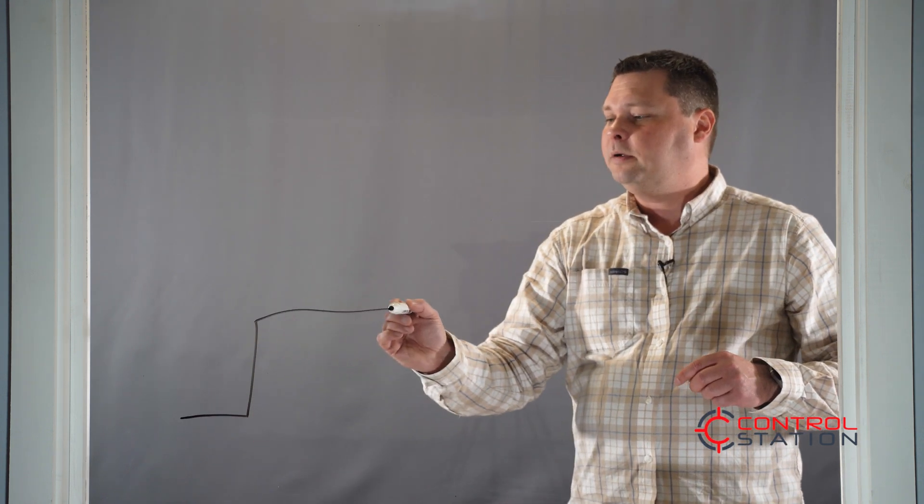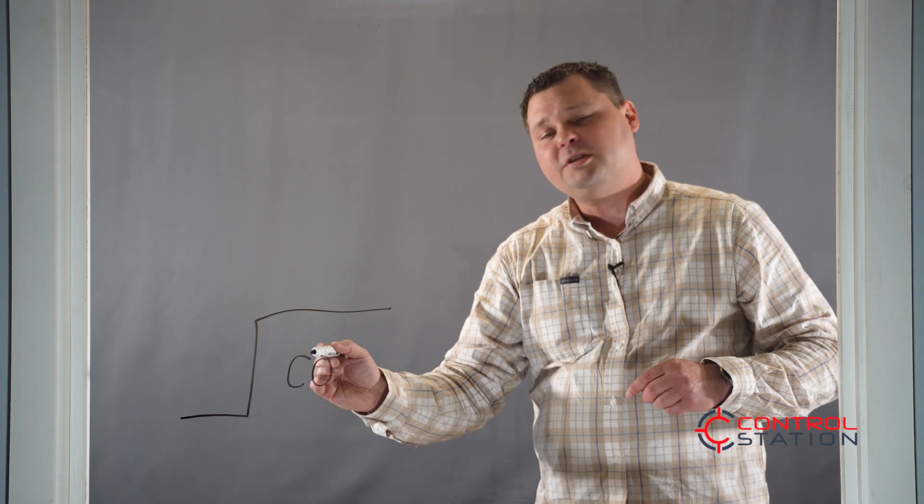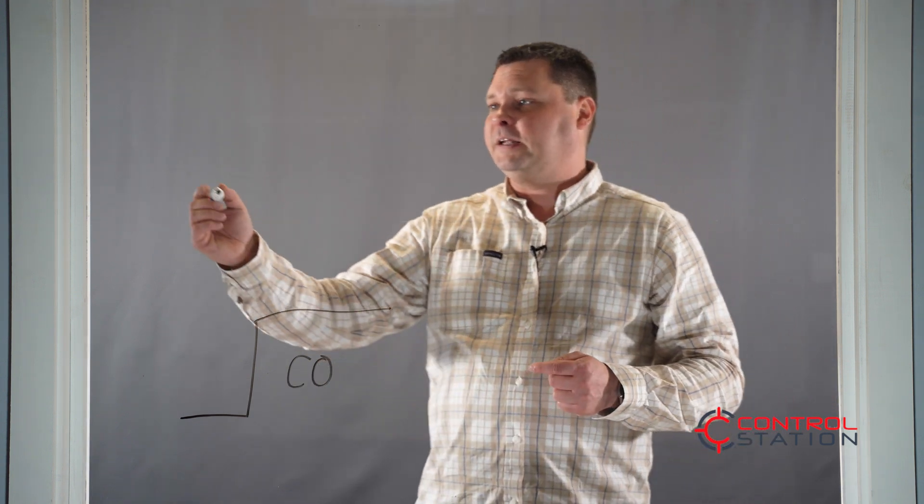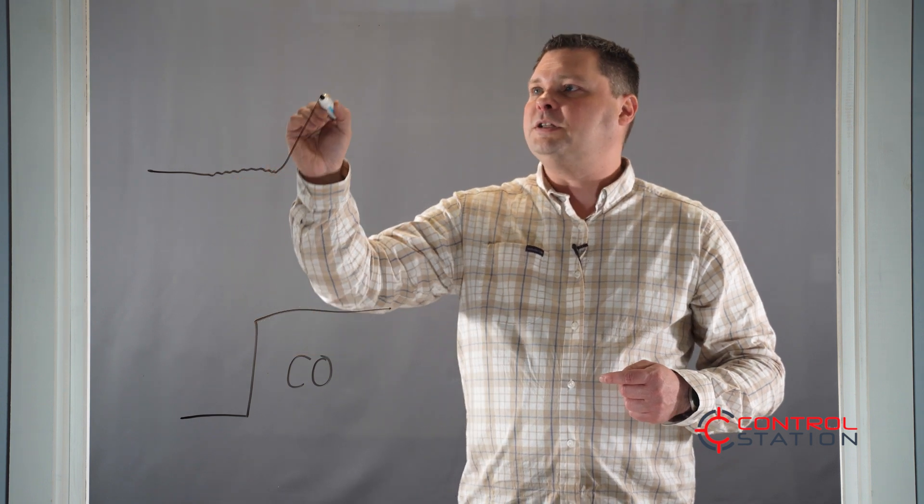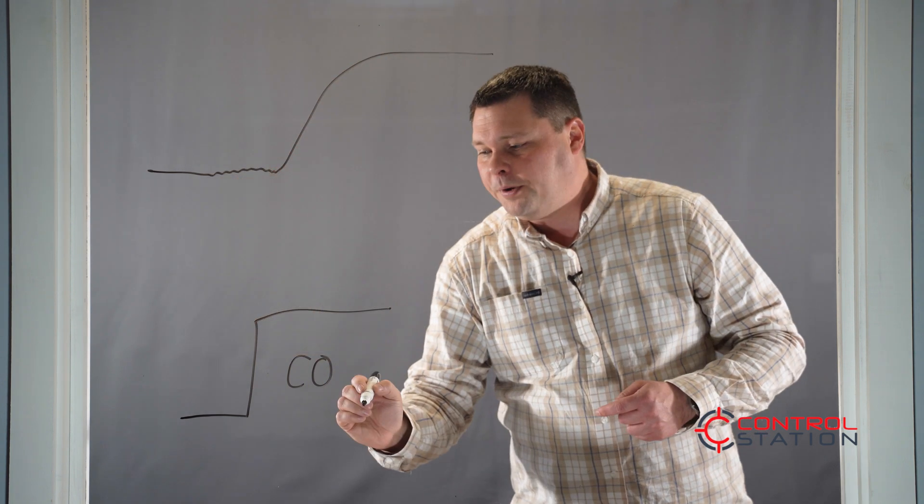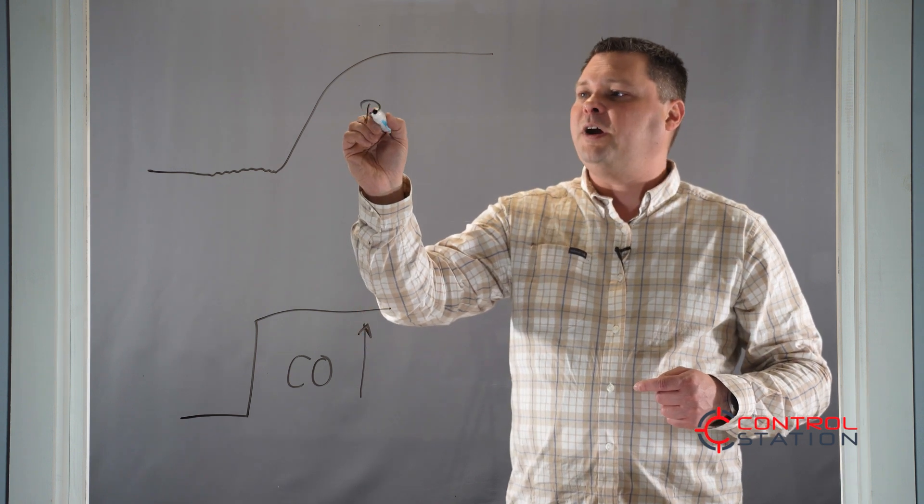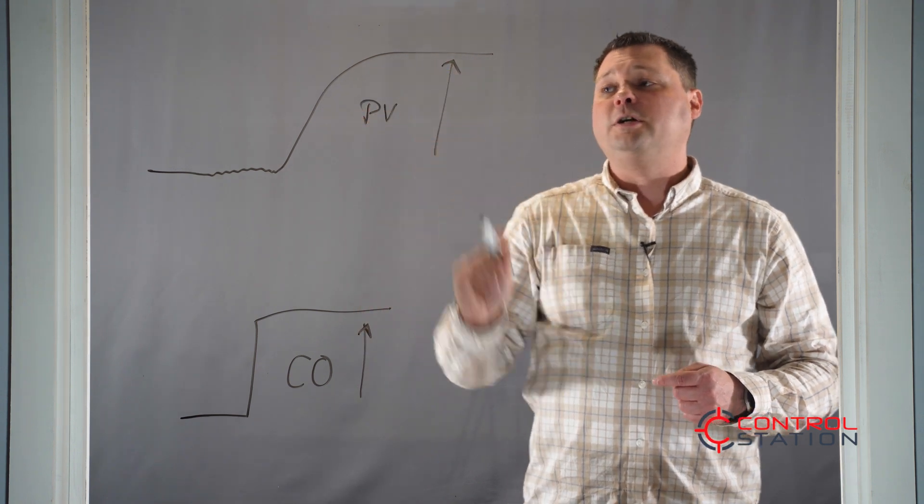So let's review a little bit. What is a bump test? For this example, what I want to talk about is a simple step test. So we step the controller output. This is our controller output. This could be a valve or a pump or something like that. And in this case, we're going to have a flow and the flow is going to change. We open the control valve and the process variable or the flow increased.